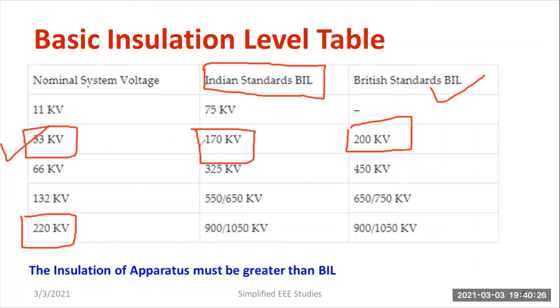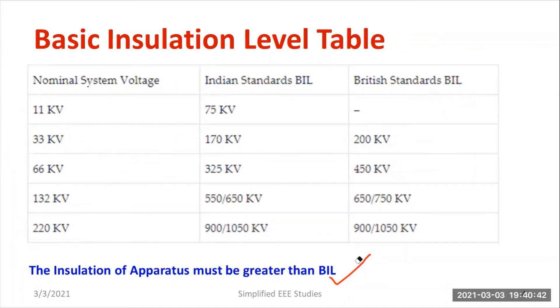This is very important. The insulation of apparatus must and should be greater than BIL. Whenever you are designing an insulator or dielectric material, you have to take care of BIL. Based on the BIL, you provide the dielectric breakdown strength for that particular insulating material. It is applicable for all types of equipment, like transformers and switchgear.